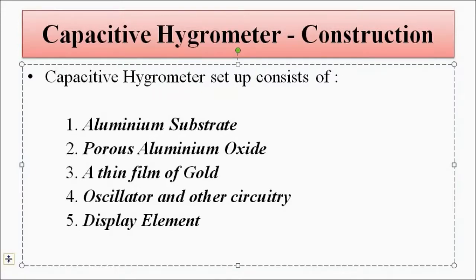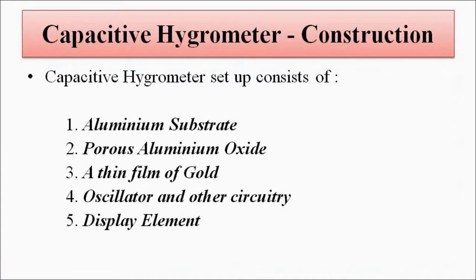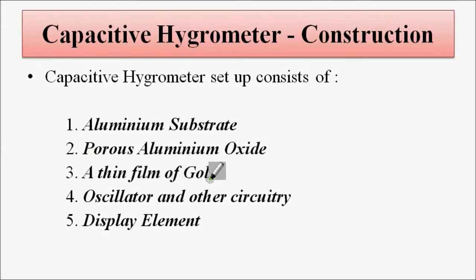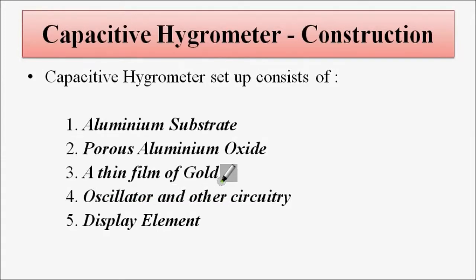The capacitive hygrometer setup consists of an aluminum substrate, porous aluminum oxide, and a thin film of gold. For signal conditioning we can use an oscillator circuit or any other AC bridges, because we have to convert the capacitance change into an output — either in terms of frequency change with the help of an oscillator, or voltage or current with the help of suitable AC bridges — and a display element.